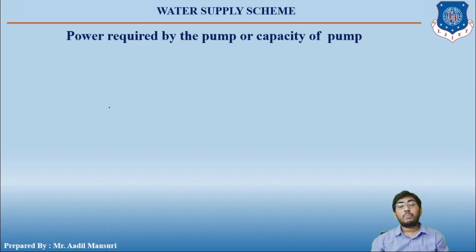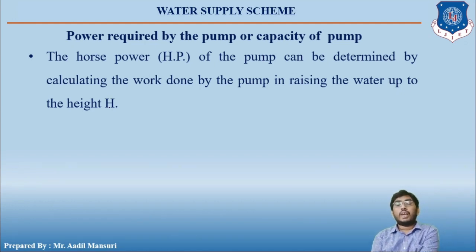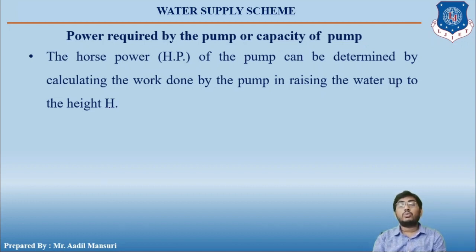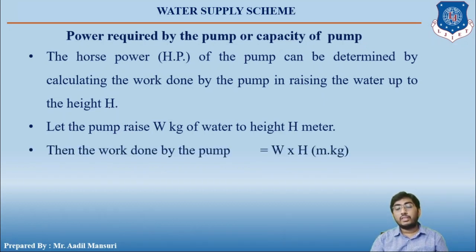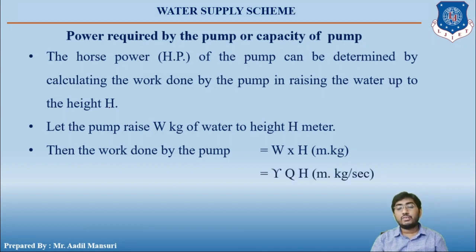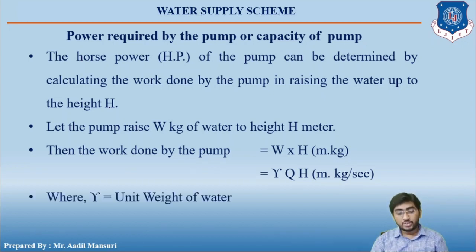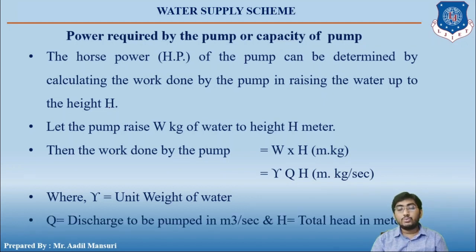Now let us talk about the power required by the pump. The horsepower of the pump can be determined by calculating the work done by the pump in raising the water to height H. If the pump raises W kg of water to height H meters, then the work done equals weight times height. Replacing weight with density times discharge gives: γQH, where γ is the unit weight of water, Q is the discharge in m³/s, and H is the total head in meters.